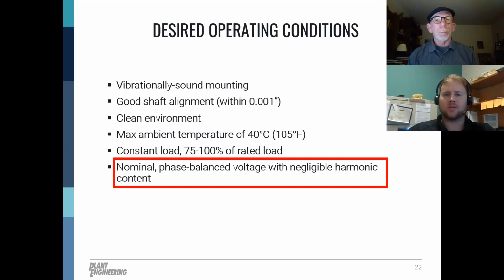So you may notice that most low voltage motors, and mainly we're talking about low voltage here, but some of this applies to medium voltage also, are rated for 230 volt, 460 volt, or in some maybe older systems, 575 volt. But typical low voltage distribution levels from the utility may be 240 volt, 480 volt, and 600 volt.